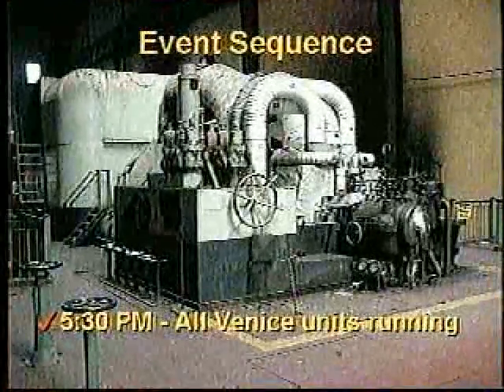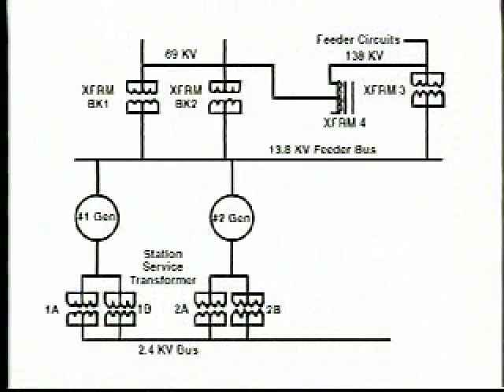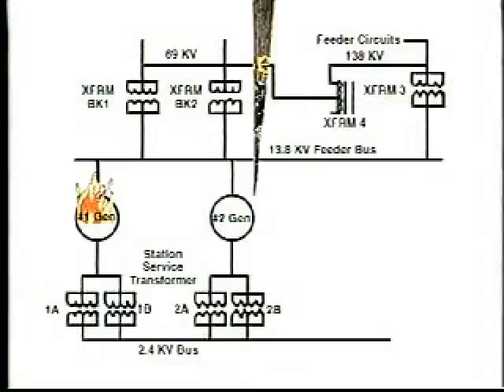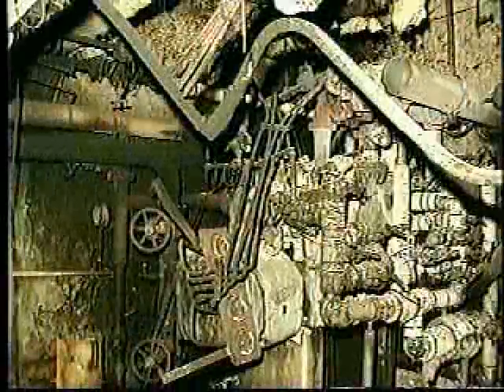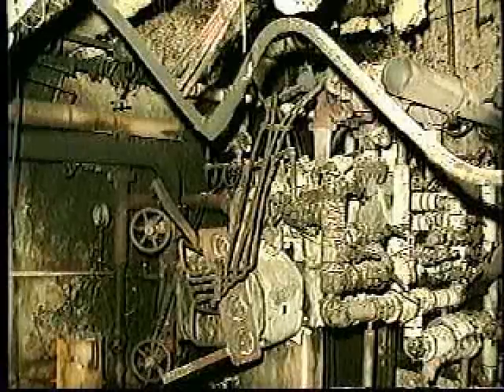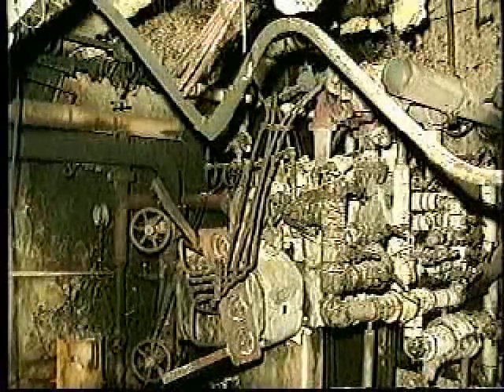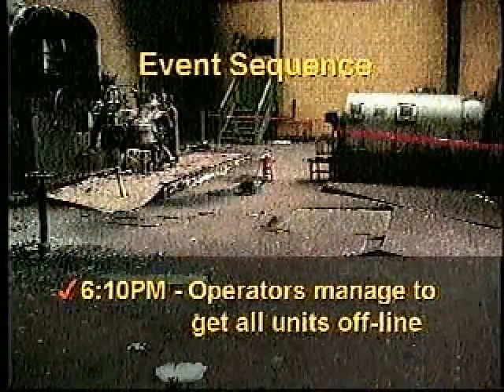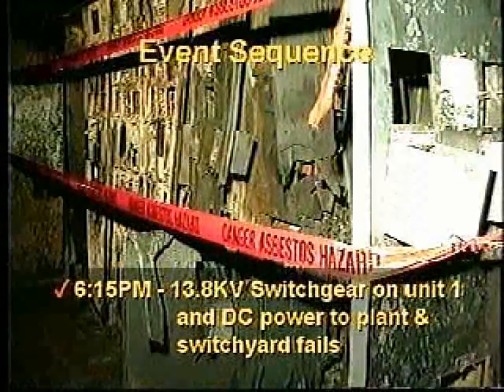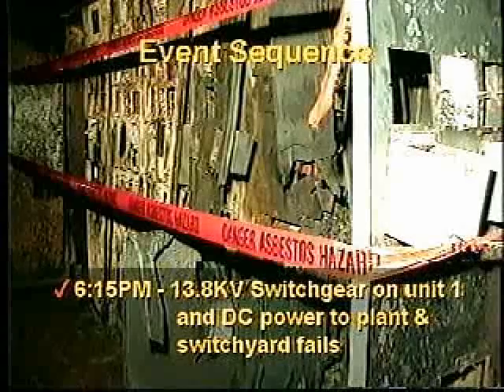Looking at the sequence of events now, at 5:30 p.m. all Venice units were running. Here we see a simple one-line of the Venice plant showing the transformers and the generators that are involved in this fire. The fire actually starts on Unit 1. At 5:55 p.m. a lube-oil line on the front of Unit 1 generator ruptures and the fire starts. Above we see damage in the area underneath the turbine generator on pipes and electrical conduit. At 6:10 p.m. operators managed to get all of the units offline. At 6:15 p.m.